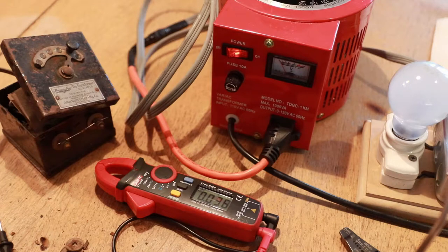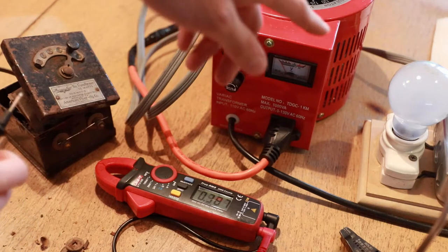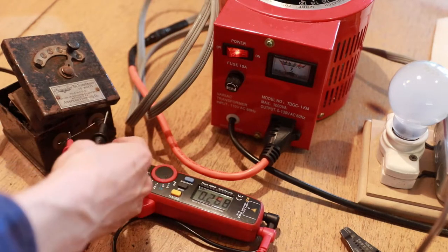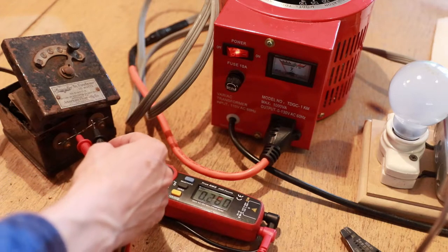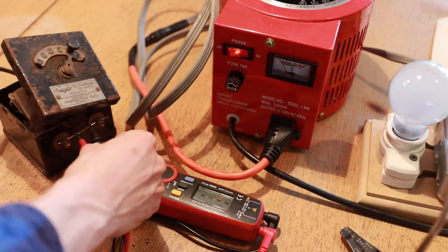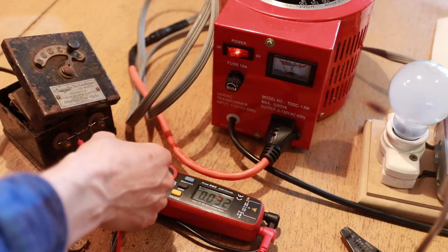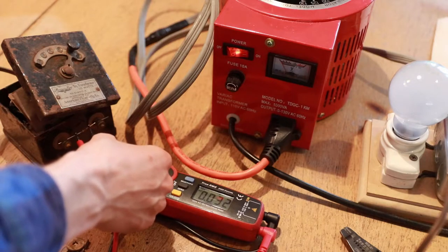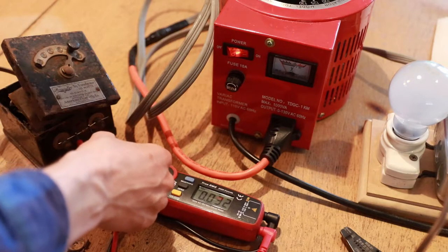This time I wired it in series with a 60 watt light bulb, that way we can see if it's drawing excessive current. The bulb might glow even under normal operation since the transformer will have some magnetizing current, but this should tell us, without creating a massive explosion, if there's a short circuit or anything like that.